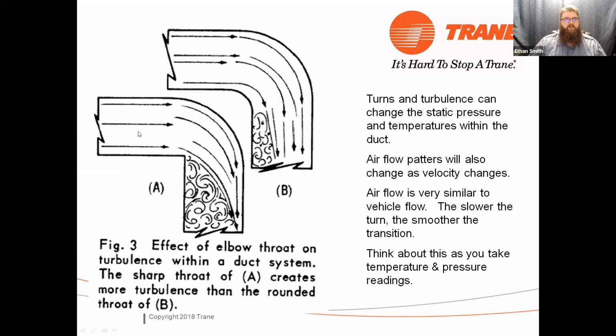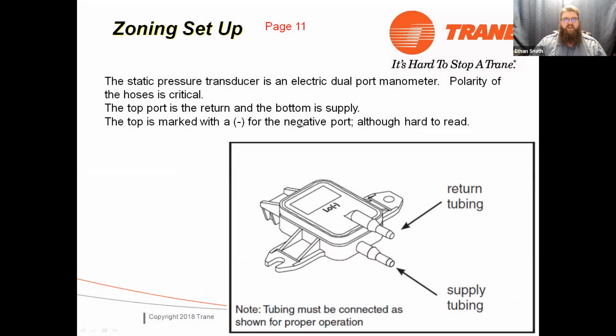Okay, so make sure when you're putting your pitot tubes, it'd be much better to put your pitot tube over here than over here. Same thing over here. Of course, you could probably put it there and be okay. It's important to get those pitot tubes in places of low turbulence so that we can get good static pressure readings. There's a nice close-up view of that static pressure sensor.